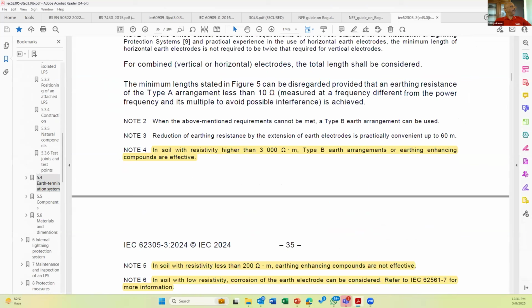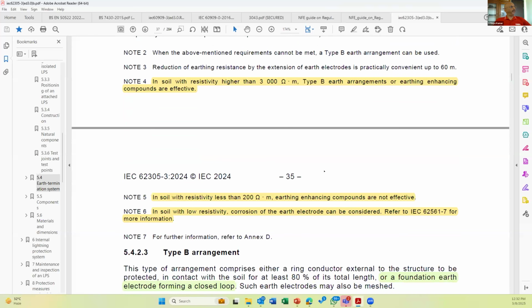Now, what is written? You see here, in soil with resistivity higher than 3000 ohm meter, that means you are in a really rocky place, Type B earthing arrangement or earth enhancing compounds are effective. If you are in a rocky place and you cannot make a Type B, that means a mesh or ring earth electrode, then you can go for an earth enhancing compound. These are sometimes called chemical earth. Number two, in soil with resistivity less than 200 ohm meter, earth enhancing compounds are not effective. If you put it in normal soil, 30 ohm meter, 50 ohm meter, the chemical actually corrodes your electrode. So less than 200 ohm meter, it is not at all effective. You don't need to use it.